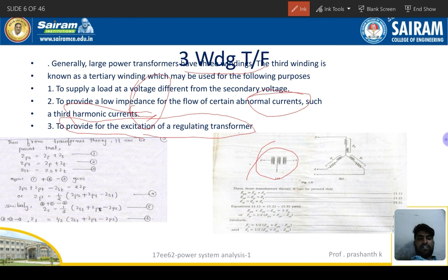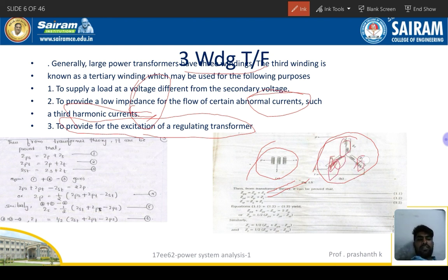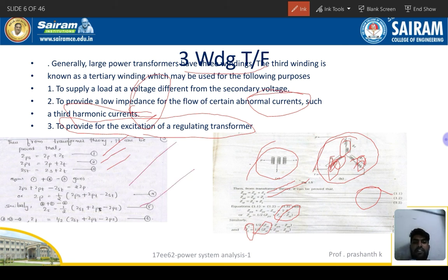For drawing the single-line diagram of a three-winding transformer, the connection is star-connected, similar to a generator. The impedance equations are: ZPS = ZP + ZS, ZPT = ZP + ZT, and ZST = ZS + ZT. By solving these three equations simultaneously, you can find ZP, ZS, and ZT separately. These are the equations used to represent the three-winding transformer in power system problems.